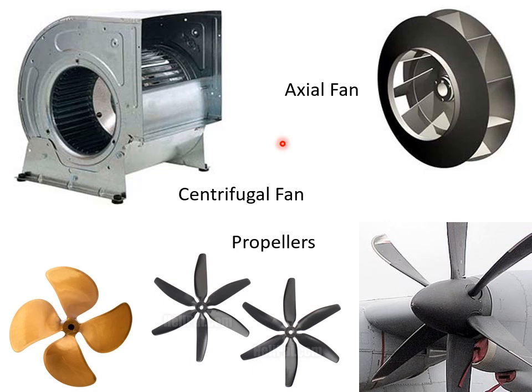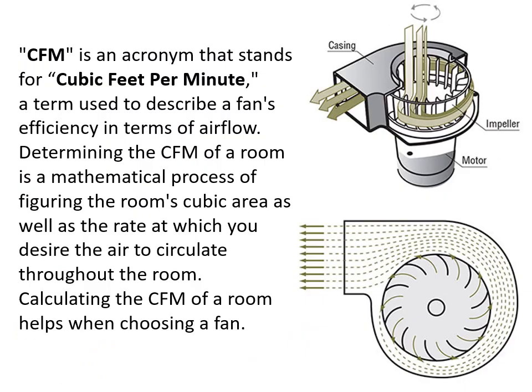There are three types of fans generally used in HVAC systems. The centrifugal fan delivers cooled air to rooms, such as in window ACs. The axial fan is generally used as an exhaust or booster fan in HVAC ducts and is also used to dissipate extra heat from condenser coils to the environment. CFM stands for cubic feet per minute, a term used to describe a fan's air flow efficiency. Determining the CFM of a room involves calculating the room's cubic area and the desired air circulation rate, which depends on the ventilation rate in air changes per hour.